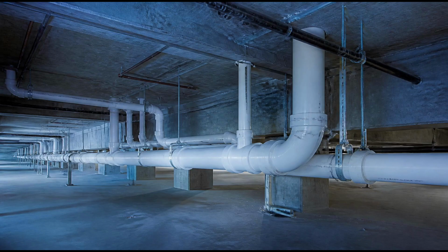Beneath every building's drainage system, and in the municipal sewer network beyond it, there are gases. The biological processes that occur as organic waste decomposes produce methane, hydrogen sulfide, carbon dioxide, and other compounds. These gases exist throughout the drainage network and, given an open path, would travel upward through the pipes and into the occupied spaces of the building. Sewer gas is not merely unpleasant in odor. Some of its components are toxic, and in sufficient concentrations, certain gases are flammable.